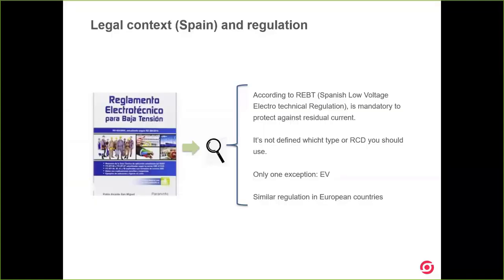Let's see how to choose according to the standards — quite similar across European countries. In Spain, we have the Spanish low voltage electrotechnical regulation (reglamento electrotécnico de baja tensión), which is mandatory across the country. That regulation states it is mandatory to protect against residual current, but does not specify which type of RCD you should choose — with only one exception: electrical vehicle recharge.